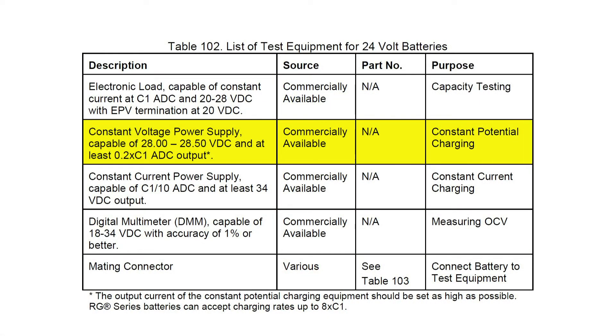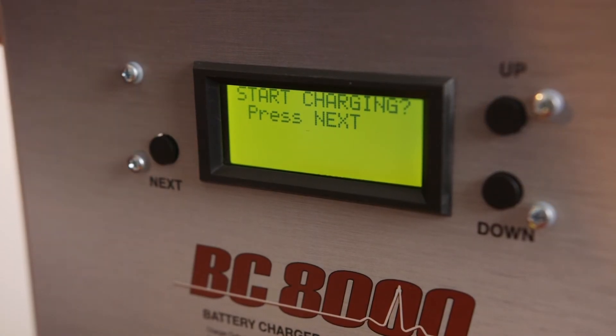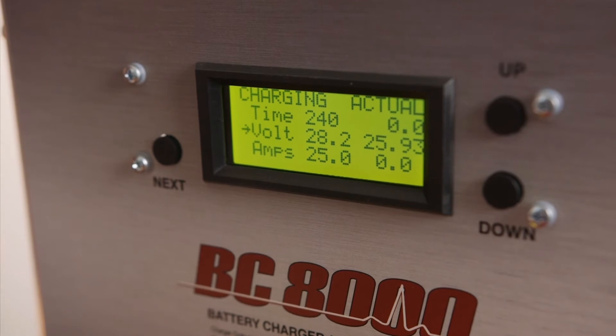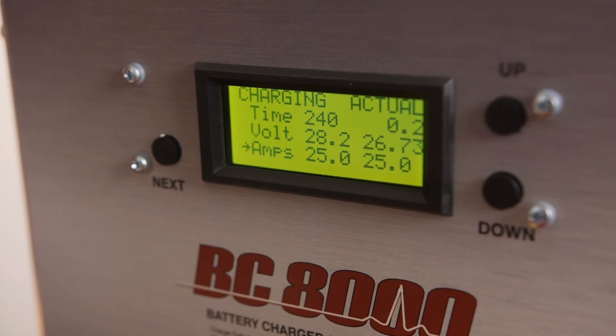Per Table 102 of the CMM, the current needs to be at least 20% of the C1 rate. For this battery, the C1 rate is 42 amps, so the charge current needs to be at least 20% of 42, or 8.4 amps. However, it is best to use the maximum output of 25 amps to cut down on the charging time. With these settings in place, we can now start the charge cycle. As you can see, the battery is charging at a voltage level above 24 volts and a current of 25 amps. Once the battery voltage reaches 28.2 volts, the voltage will be held constant at this value and the current will taper down to a very low level. We'll come back in 4 hours when the charging cycle is complete.